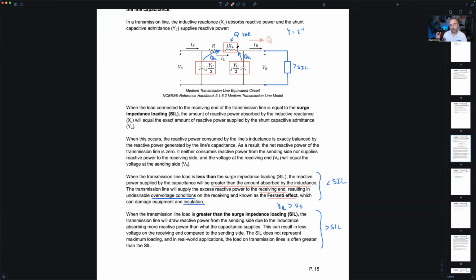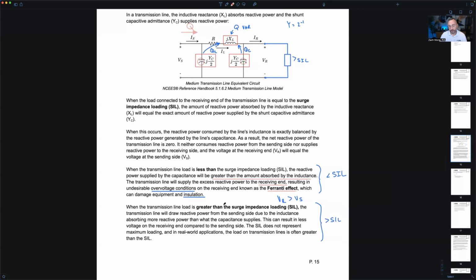This series inductor right here, depending on how big that reactance is, has a set amount of reactive power that it's going to consume when current flows through it. So if those needs are not met by the reactive power being supplied from here and here, then instead of exporting reactive power to the receiving side, it's going to draw reactive power from the sending side. In other words, there's not enough reactive power to completely satisfy it. We don't have quite enough. So instead, it's going to pull some from the sending side. Again, these are concepts similar to excitation when we're dealing with synchronous machines, and overexcitation and underexcitation. Are we exporting VARs? Are we importing VARs? What happens then? Now, instead of the receiving side being greater than the sending side, the receiving voltage is going to be less than the sending voltage.